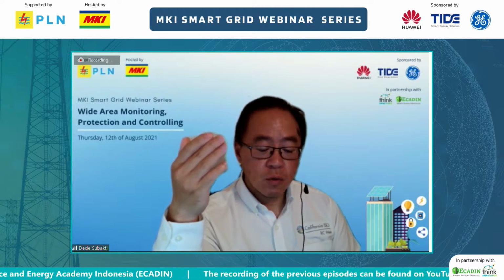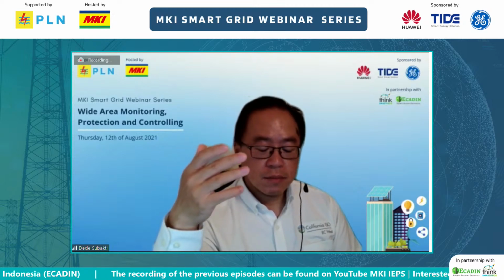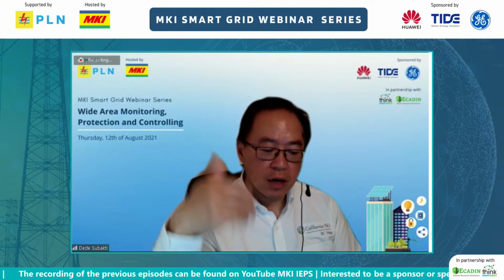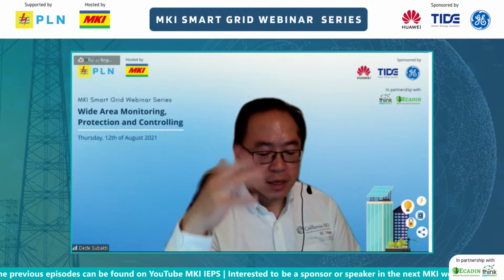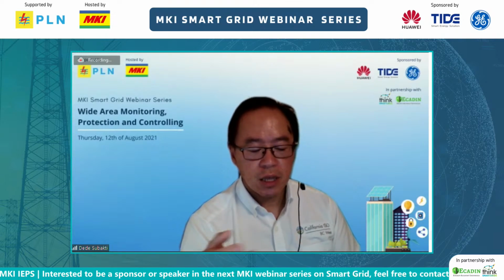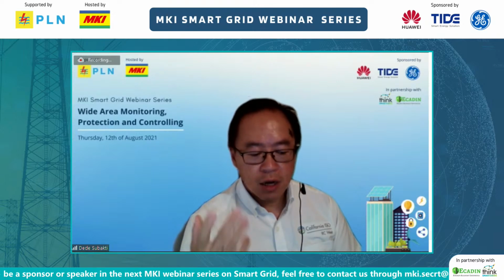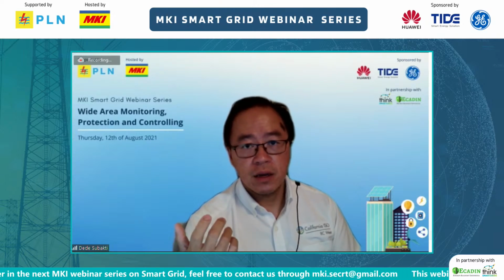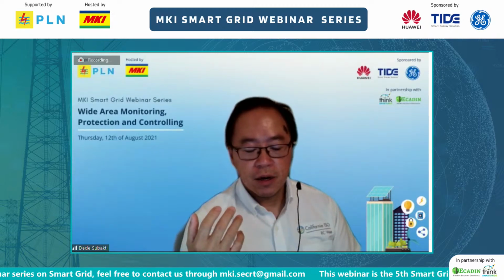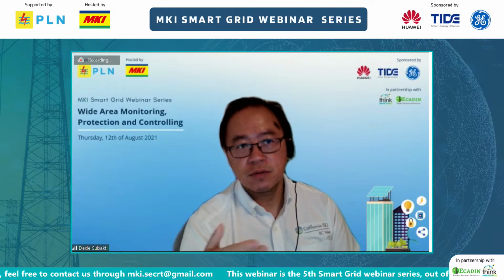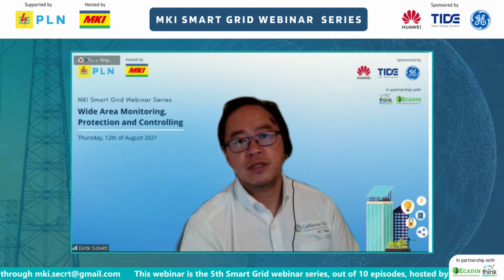The inter-area oscillation that is very common is when you send too much power, or when you send a lot of power from the northern, the Pacific Northwest, which is Oregon and Washington, down to California. There's a bunch of 500 kV lines, and it's actually a long line. And you could have that quarter hertz oscillation, and then you'll get an alarm. And if the alarm is there, what we've studied and analyzed is that there are things like, of course, reducing the power transfer by redispatching units that would work, but that's normally very expensive.